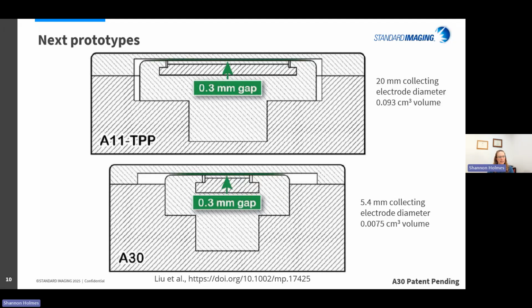Up to what dose is the detector linear with delivered dose? That depends mostly on dose per pulse. So we've looked at dose per pulse in a 4 microsecond pulse up to about 9 gray per pulse. If your pulse is broader than 4 microseconds, then it's easier to measure the dose at a higher dose per pulse. But the narrower that the pulse width is, the more challenging it is for the chamber. So we were looking at still 95% collection efficiency up at that 8 or 9 gray per pulse.